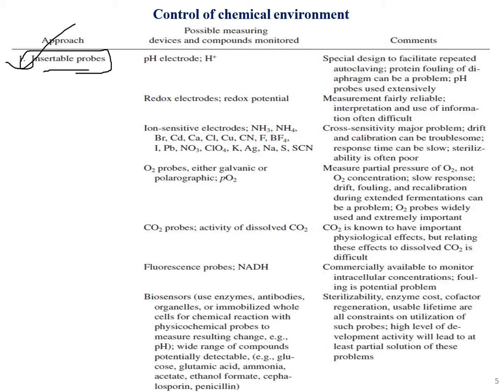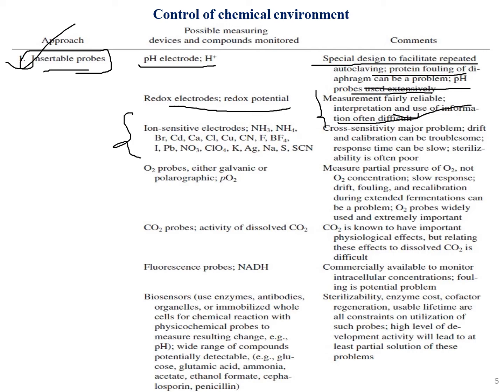Insertable probes possess a pH electrode with a special design to facilitate repeated autoclaving, though protein fouling of the diaphragm can cause problems. They also include redox electrodes — redox potential measurement is fairly reliable, though interpretation of the information is often difficult. Ion-sensitive electrodes can measure ions such as NH3, NH4, and many others.